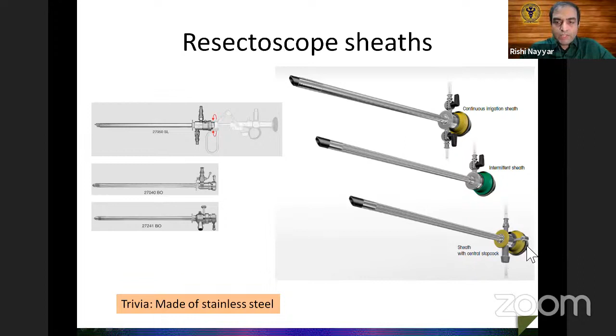The resectoscope sheaths that are commonly used are 26 or 27 French. These details would vary according to the manufacturer; minor variations may be there. The working length is most of the time 20 centimeters for a standard resectoscope sheath. The outer sheath can be identified by the presence of multiple fenestrations that you can see at the distal end of the sheath. This continuous irrigation outer sheath also has two channels, one for the inlet and one for the outlet.